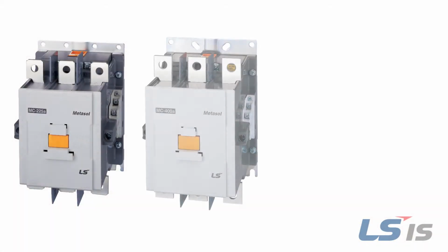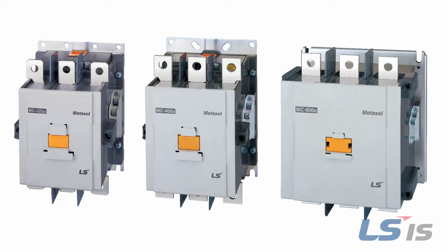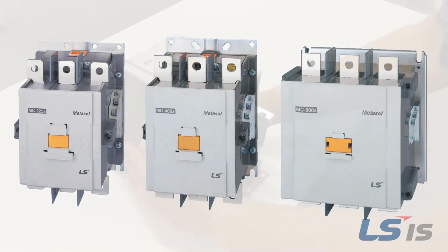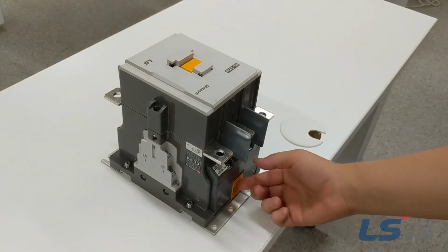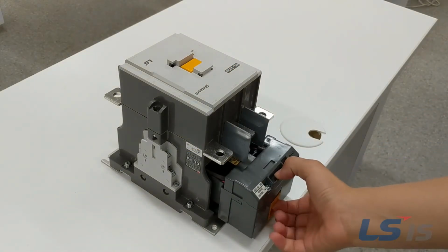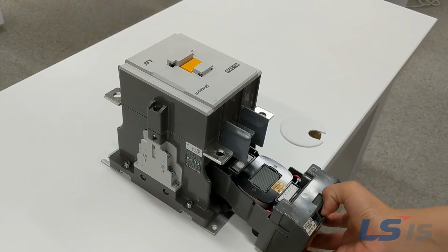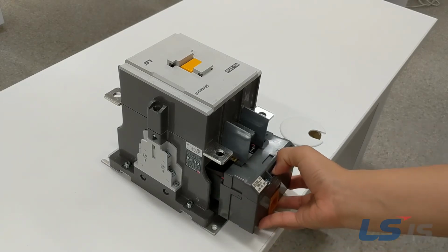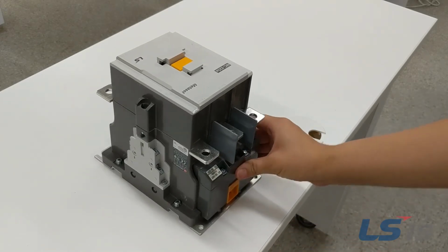For the MC-225a frame to MC-800a frame contactors, remove the contactor from the box and lay on a flat surface. Locate the orange coil locking mechanism, push it up, and pull out the coil. To install the new coil, simply slide the replacement coil into the contactor housing and make sure the coil is fully seated.